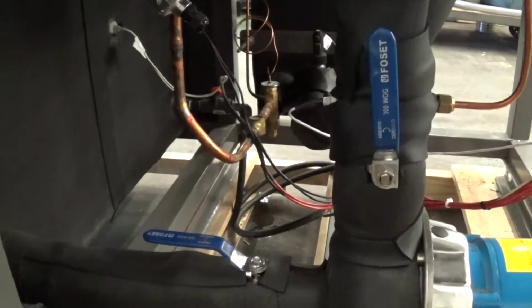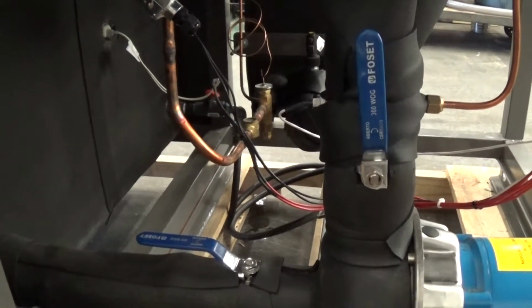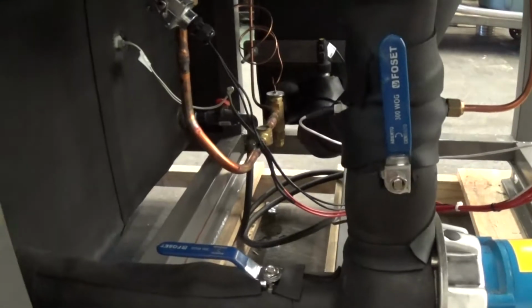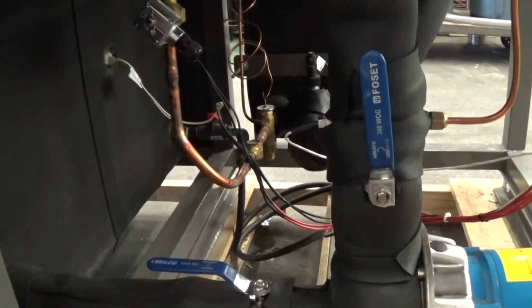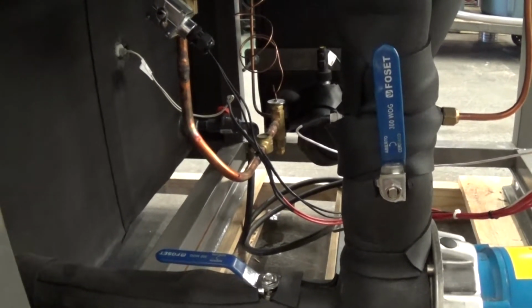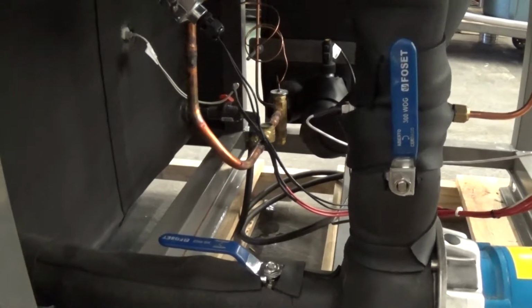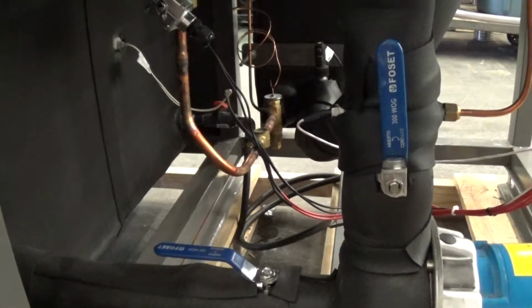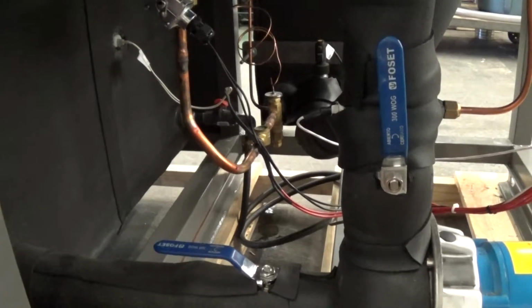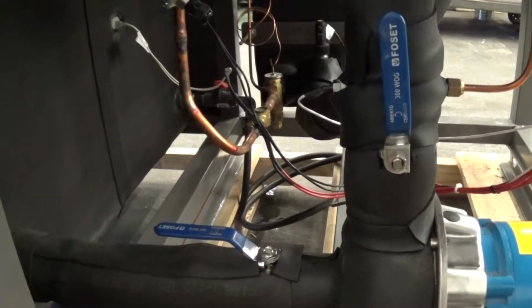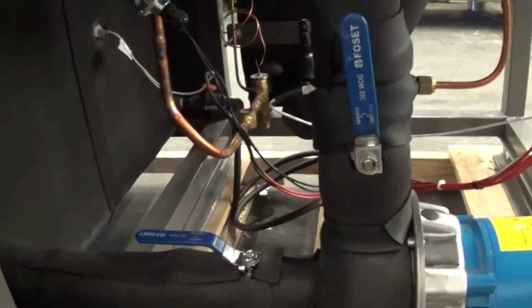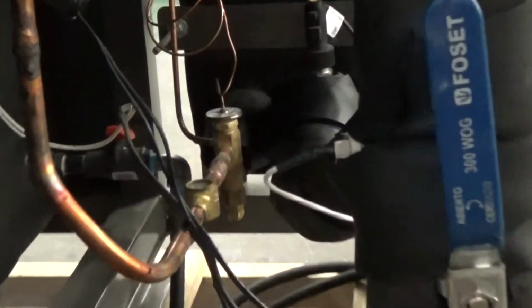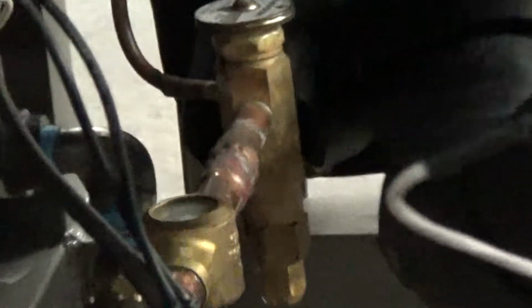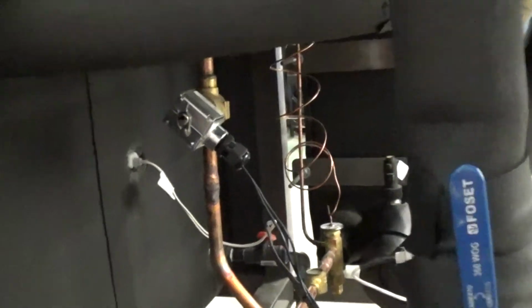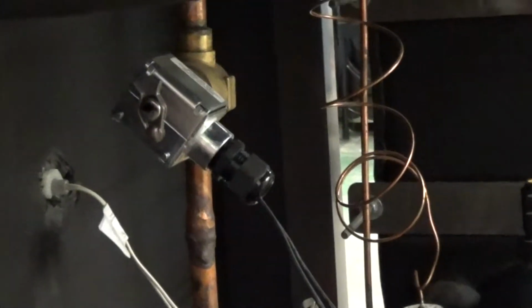For that reason, there'll be a little bit of a fluctuation because the water is always going through the heat exchanger, but it's only when the compressor is on that you're going to see cooling. However, we're sensing the tank temperature, and things kind of average out. We may have to ultimately play with the differential setting on the controller to meet a happy medium for your set point temperatures. There's our thermal expansion valve and a refrigerant sight glass and a positive line shut off for the refrigerant.